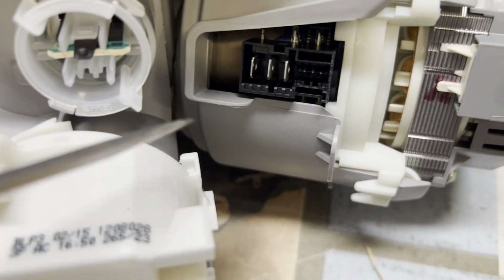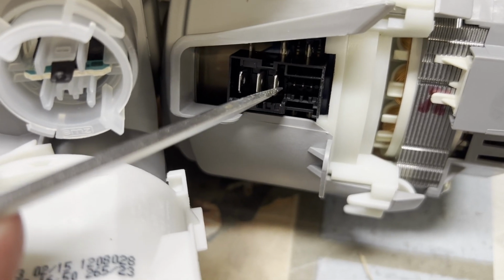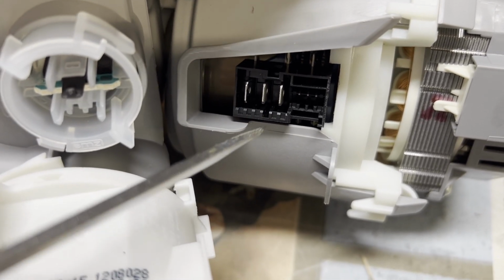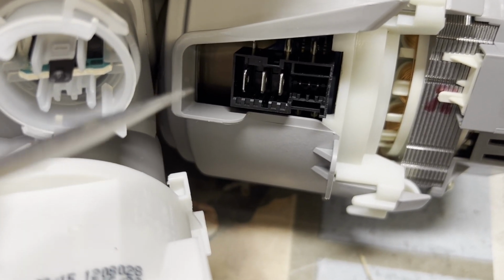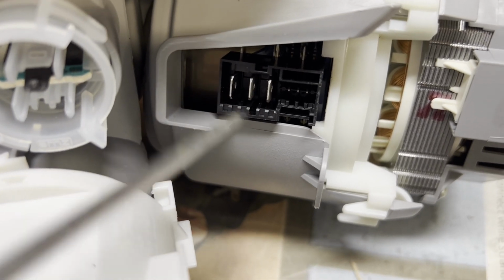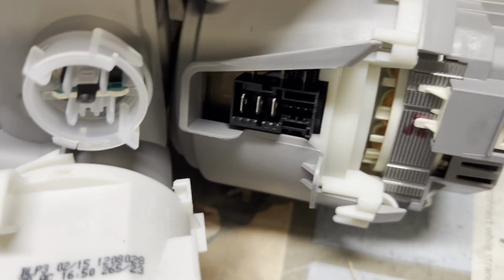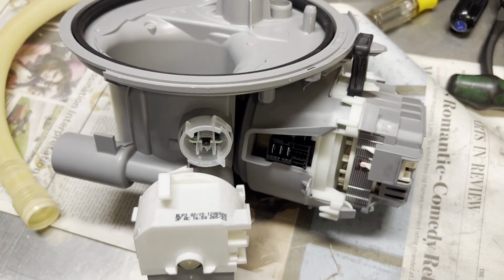The way to test this pump is to ohm out these two connections right here and here. It should read either 9 or 18 ohms, depending on what country you're in. That's ground, and it'll tell you if the pump is shot or not. So anyway, that's this guy.